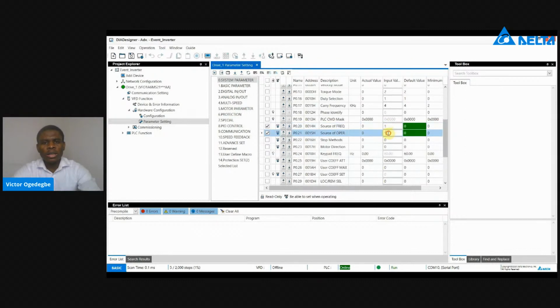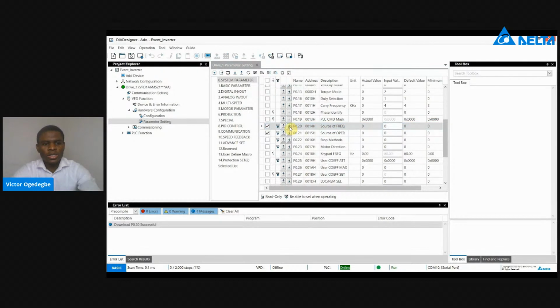You see, I'm going to download in a moment. If you look at the bottom screen, you will see that the download will be successful. It's just a single parameter. You can see the download is successful. So with one software, you easily configure the VFD parameter. Also, with this same software, you can also program the internal PLC of the inverter. In the past, we did this with two software. But now, thanks to DIADesigner, with one software, you save time and you can do this.